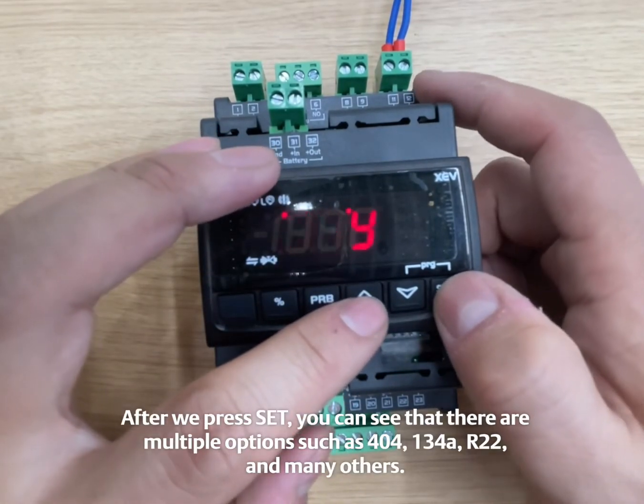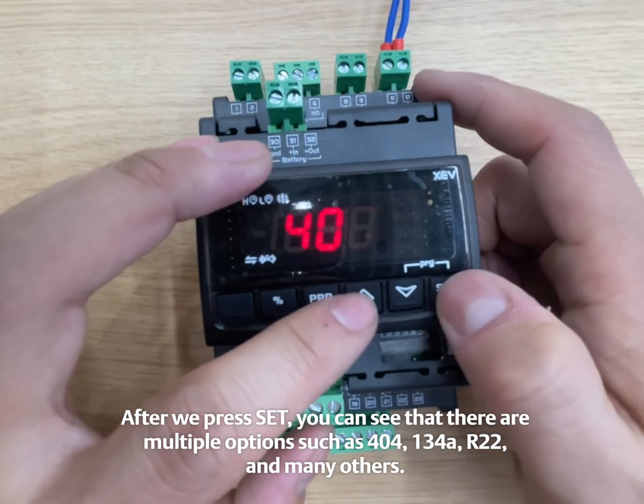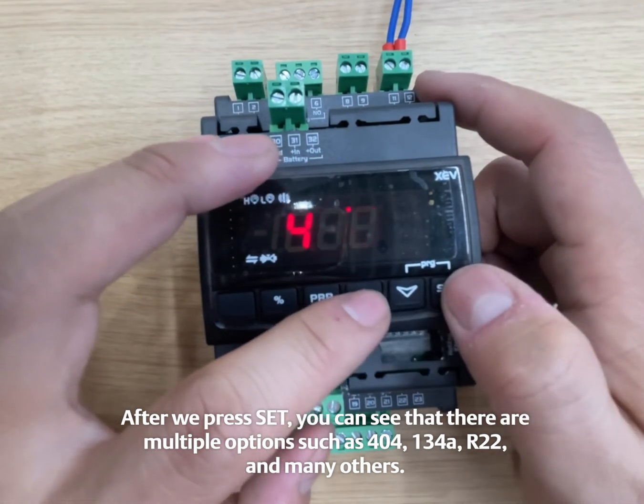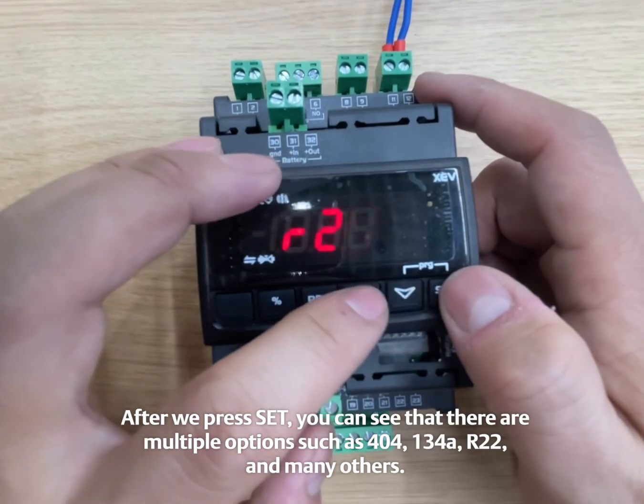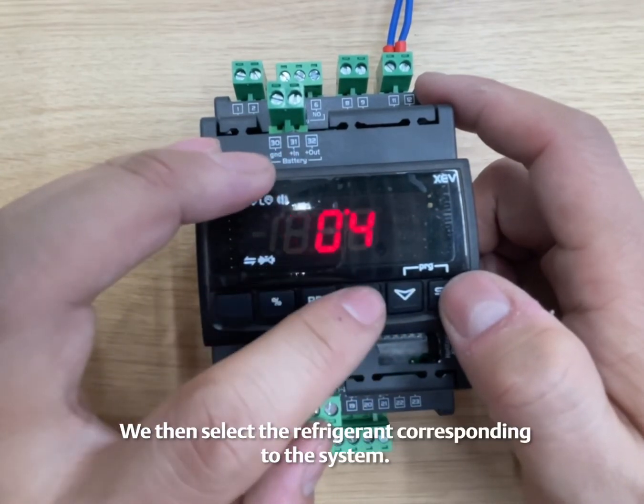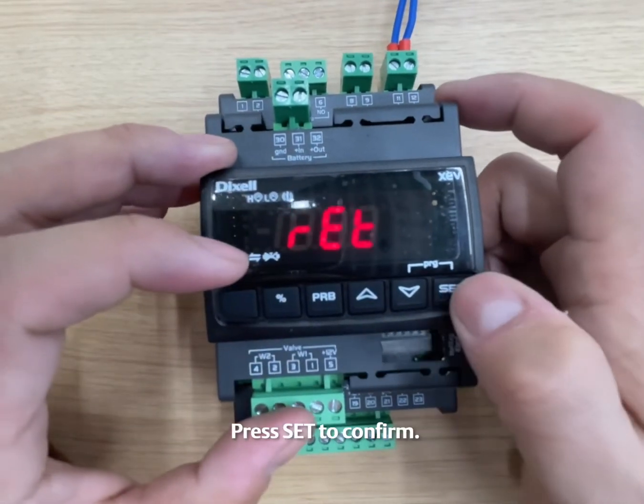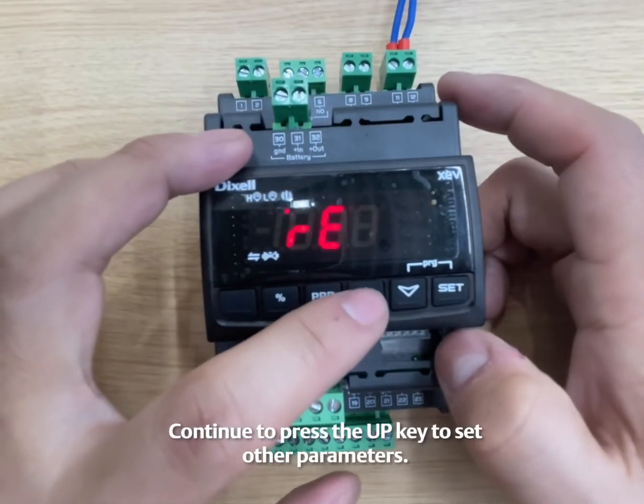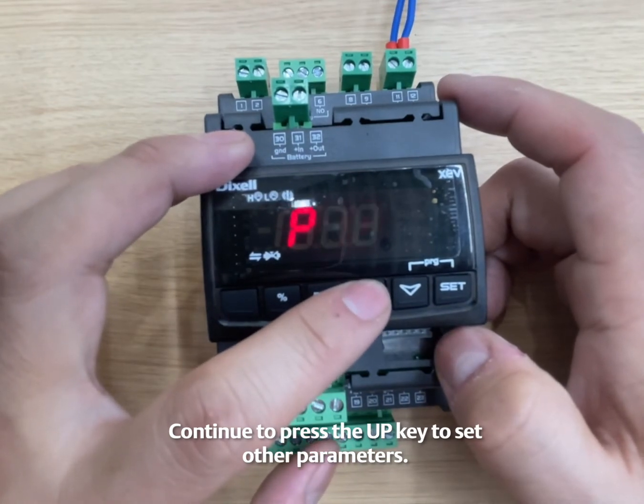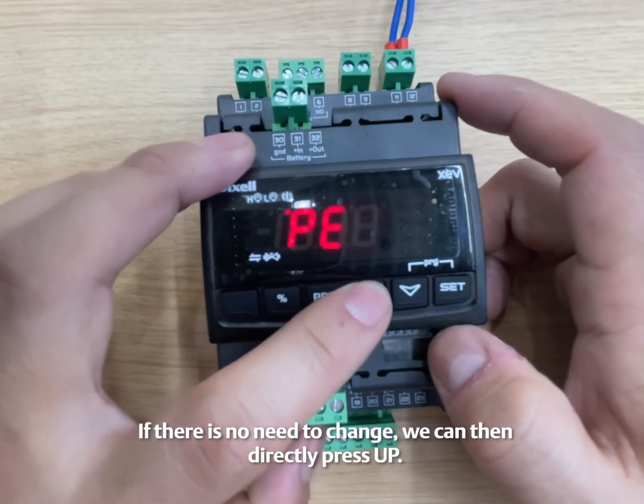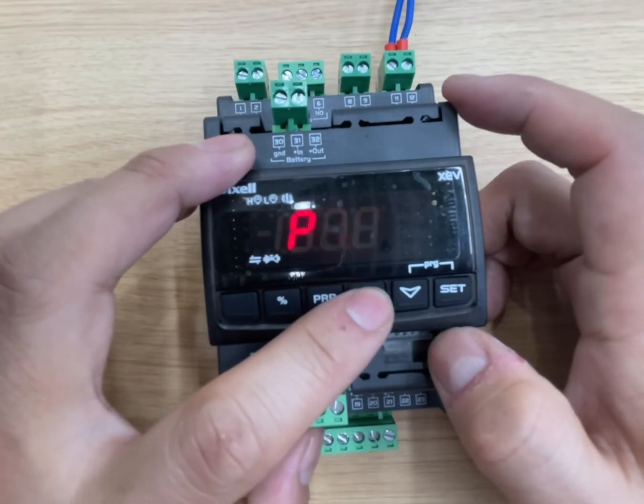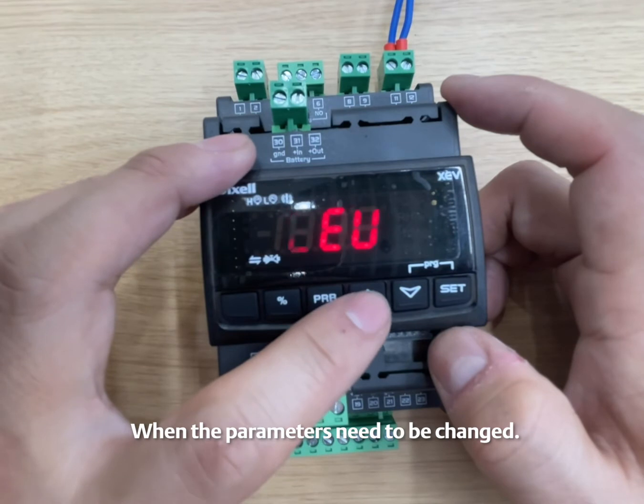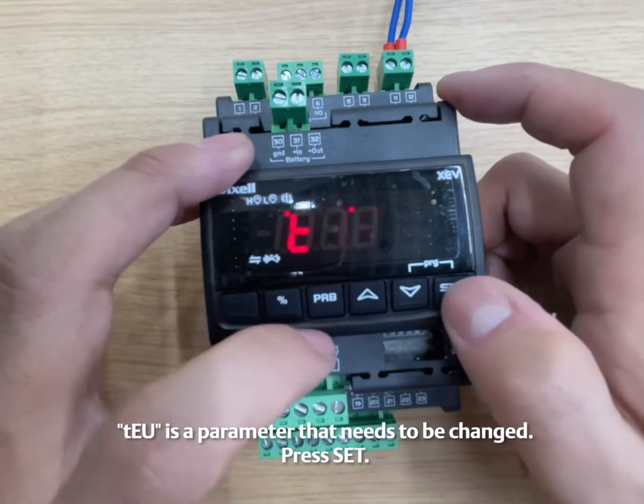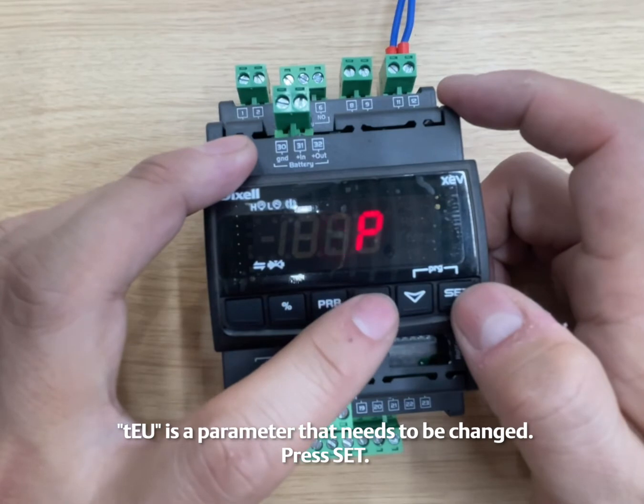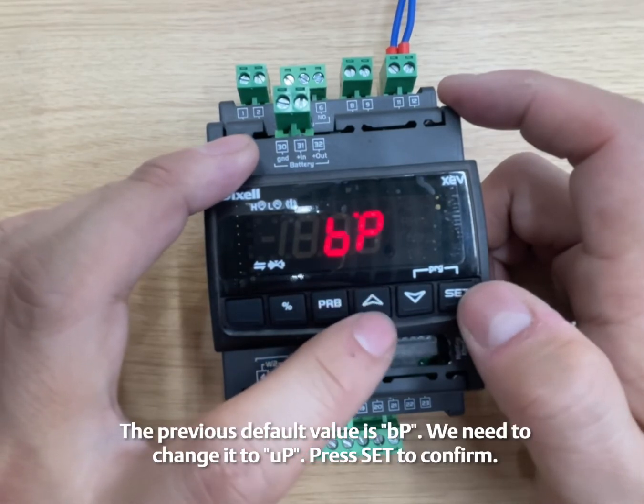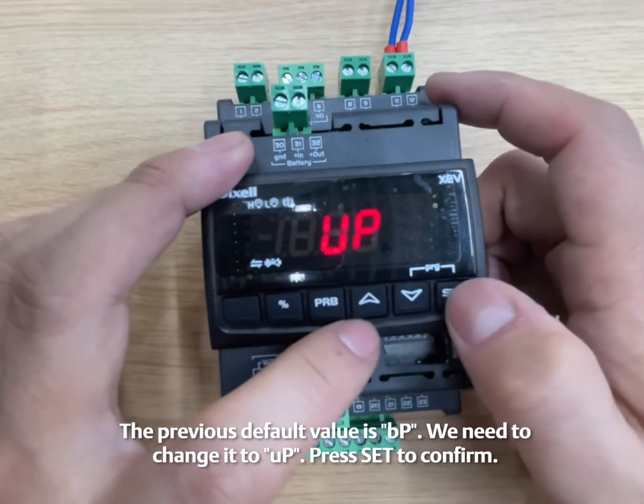After we press set, you can see that there are multiple options, such as 404, 134A, R22, and many others. We then select the refrigerant corresponding to the system. Press set to confirm. Continue to press the up key to set other parameters. If there is no need to change, we can then directly press up. When the parameters need to be changed, TEU is a parameter that needs to be changed. Press set. The previous default value is BP. We need to change it to UP.